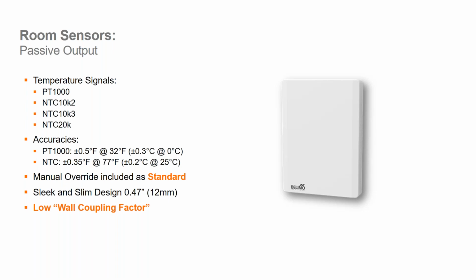A very low profile and something called low wall coupling factor, which I'll explain pretty simply. We know that sometimes there is a draft in the wall, so if the wall's not insulated, you may pick up radiant temperature from inside the wall, either through the junction box. In some cases, depending on the installation parameters, the sensor is not even mounted to a junction box. So the way it's designed is the temperature sensing element is isolated a little bit inside the housing, and it prevents it from picking up any transient temperatures that come in through the walls and things like that.